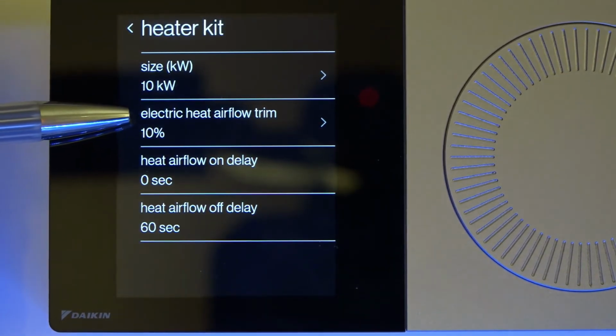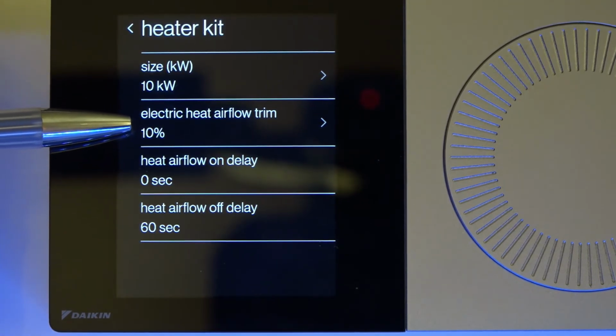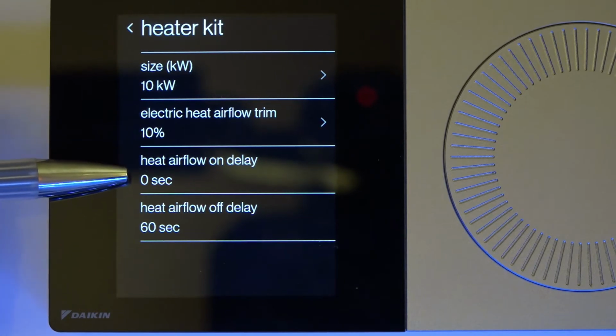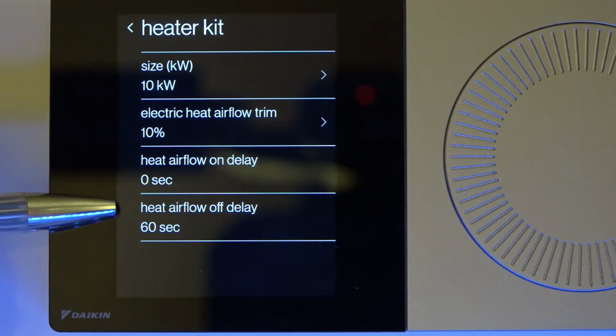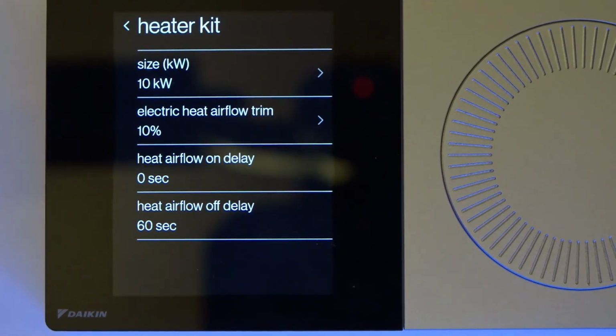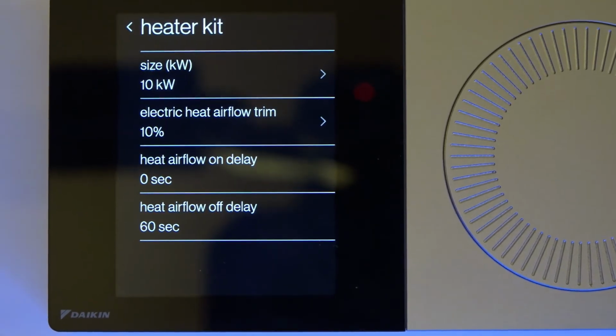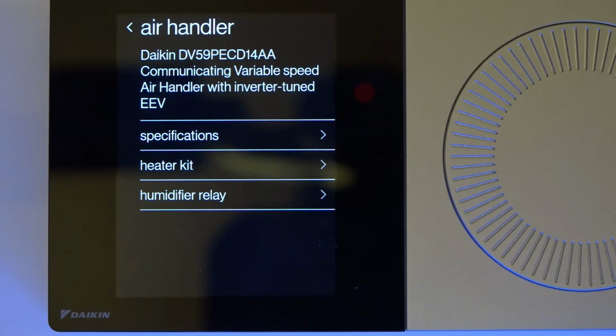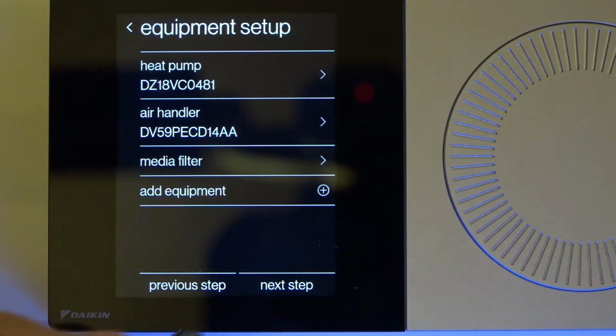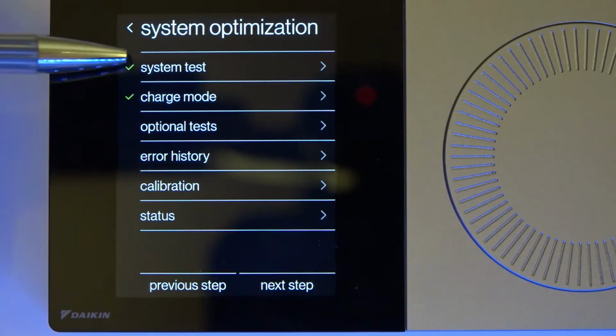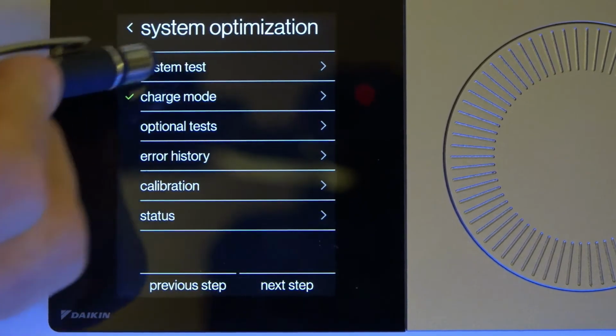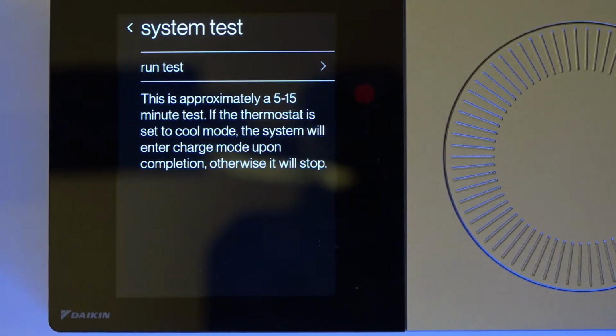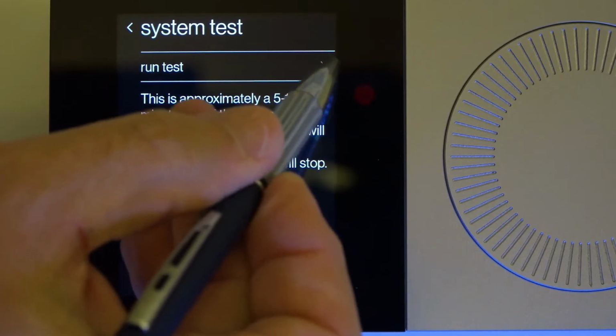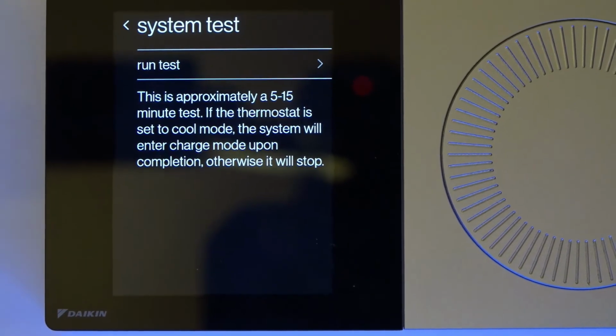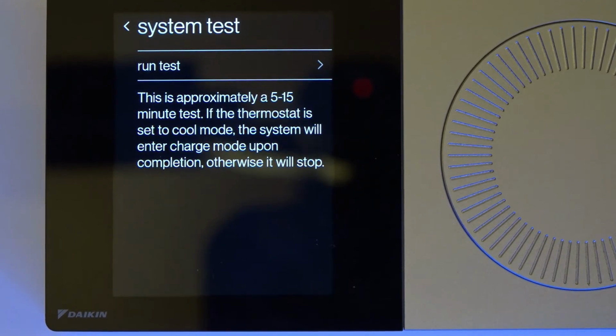And now I can have an electric heater trim if I need to trim it just a little bit. And my delay on and delay off there again. I usually leave the delay off at least 60 seconds after the thermostat satisfies. That's to cool the heat strips down and prevent them from overheating. Okay, the next step, I hit next step here. Now I need to hit the system run test. All I have to do is select run test and then hit run test, and I'll get a little spinning dial over here. This test takes about 15-20 minutes to run through.